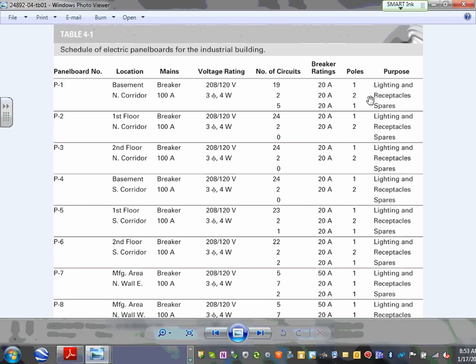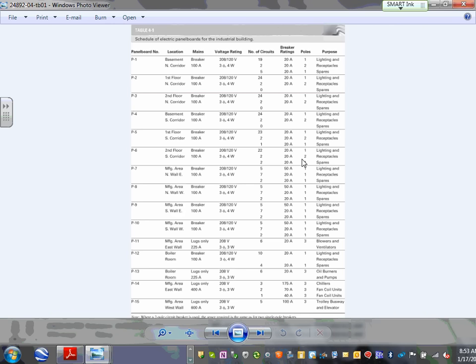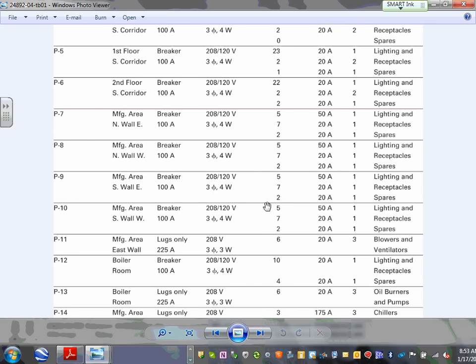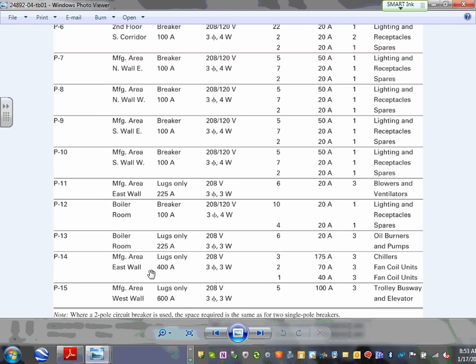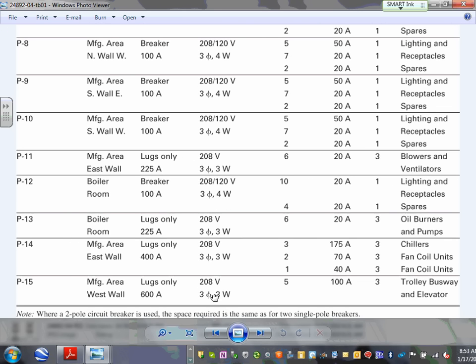Basically, these are lighting and these are receptacles. So they identify how many circuit breakers there are and what they're doing. If you look all the way to P15, there are 100 amp, 5 circuit breakers. Each one of them is 100 amp, and it's tied to the trolley busway and the elevator. So they're feeding the trolley busway and the elevator.